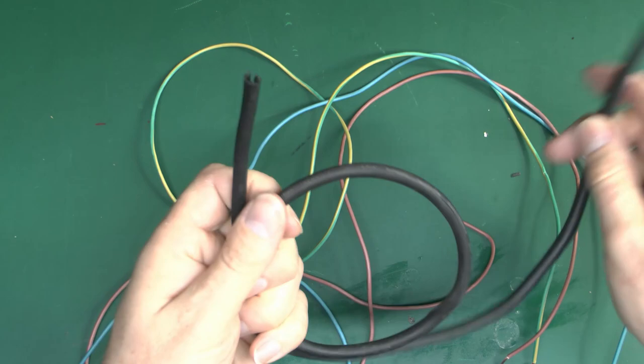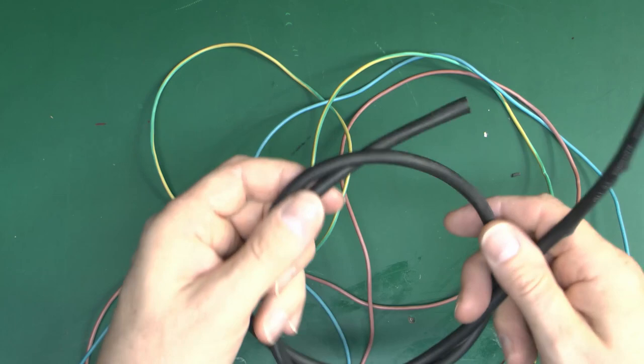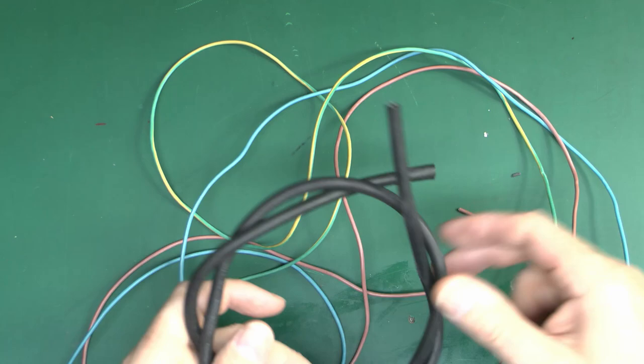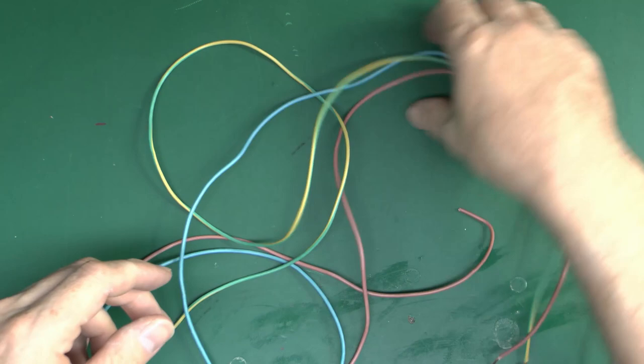So this can only be down to substandard flex, which may have been fairly poor when it was originally installed. I didn't actually install these originally and that was many years ago that they were put in, so no test results available from the original install, but certainly now it's down to a very poor level. So let's just twist these together and then we'll test it without the black covering on and see if that makes any kind of difference.